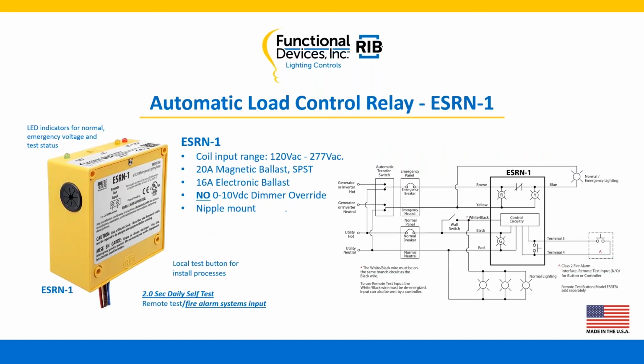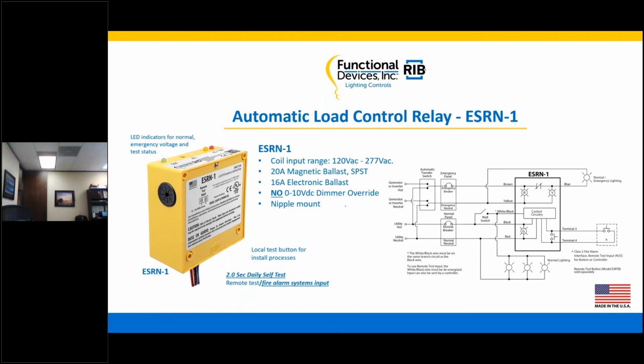Here, what we've got is what we call an automatic load control relay. We brought it in a little bit later. This particular one has features very much like the ESRN, although the key behind this one is it has no 0 through 10 volt dimming override. You get different lighting applications where some have dimming going on, some do not. So we try to provide this: why spend the extra money for the override if you don't need it? So in this application, you're doing the same thing.